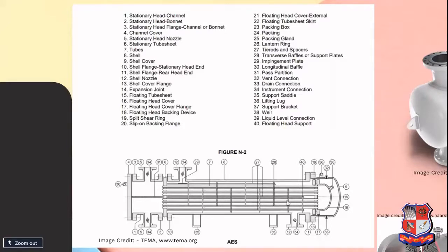Over the tubes you will have baffles. Those baffles are useful for creating turbulence in the shell side fluid, which will increase the heat transfer. And those baffles also support the tubes, and baffles are themselves supported with the help of tie rods. These tie rods are numbered 27, and they are also known as spacers, which maintain the space between the baffles.